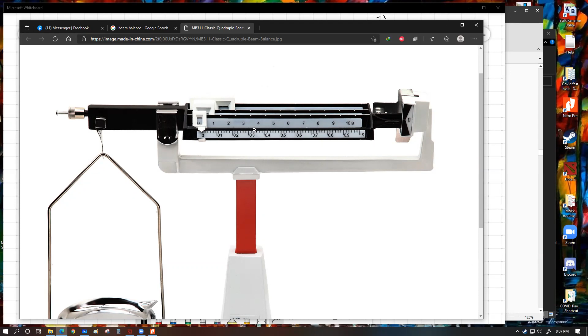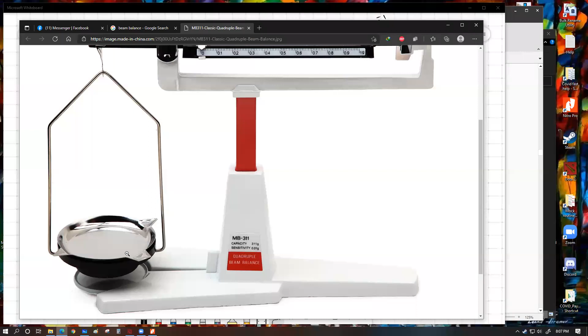The logical way to check the error that might exist within an equipment is always that we place a known mass onto this mass side. In this case, it's a single pan balance. This can also work for a beam balance as well. Beam balance usually is seen to be pretty balanced, because if you don't load anything, you just look at it, you should be able to see it perfectly horizontal. So beam balance typically doesn't get any zero error because it's so widely visible whether it has zero error or not. Where Sir, isn't it like prone to human error?